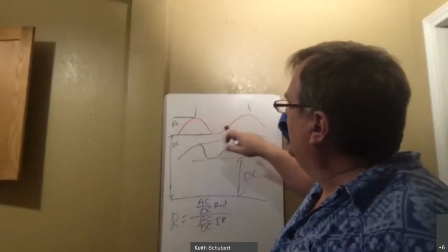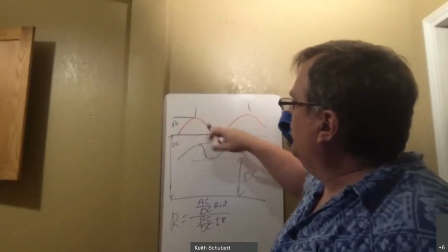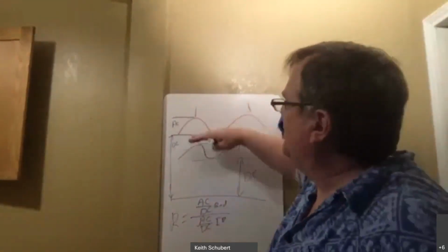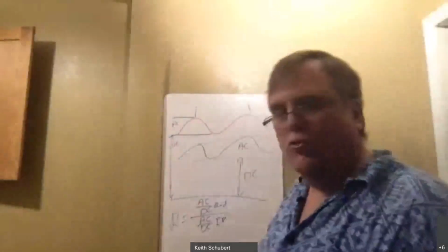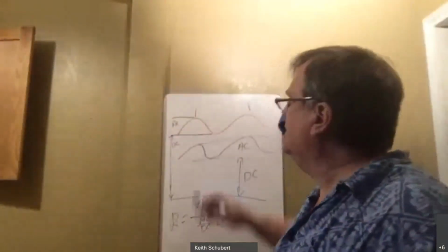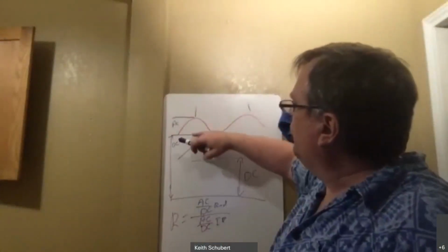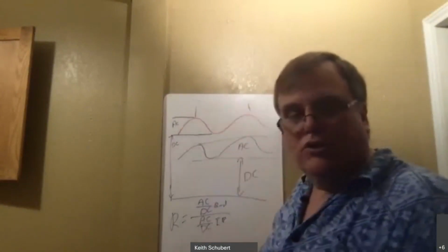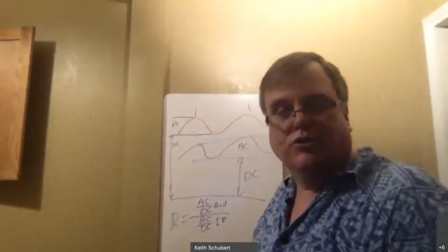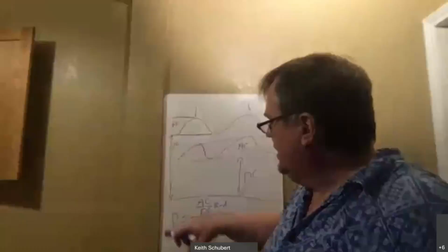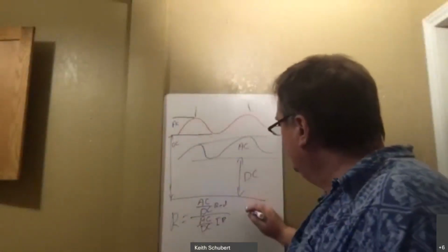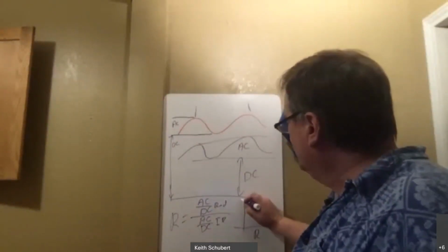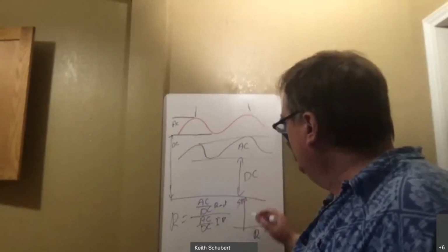So if you take a look at this heartbeat area and you smooth it, you'll get rid of the noise spikes, so you'll get a better top and bottom value. That's really the whole reason for smoothing the function, just to get the range of AC and the DC, and that's all you're reading out. And again, you can do that across a couple of them just to get a good AC and a good DC value for each. Calculate that ratio R. And then I comment that you can plot the ratio R versus your SpO2.